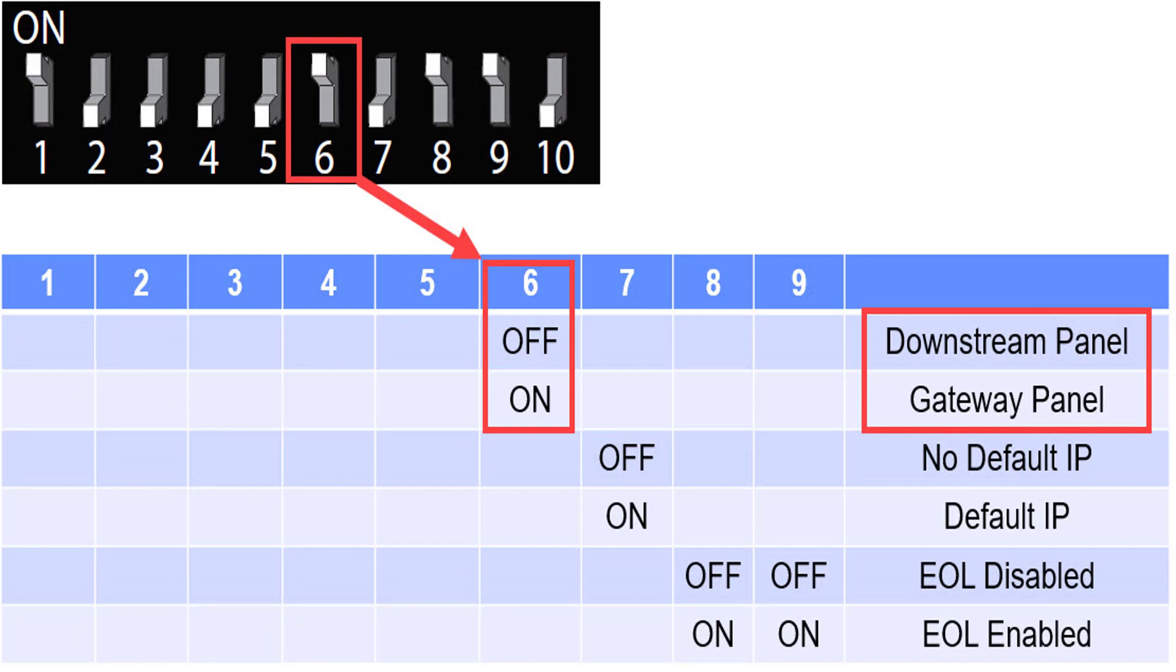DIP switch 6 enables the web interface of the panel and makes it a gateway or main panel. This must be only on on a standalone panel or the first panel of a loop.